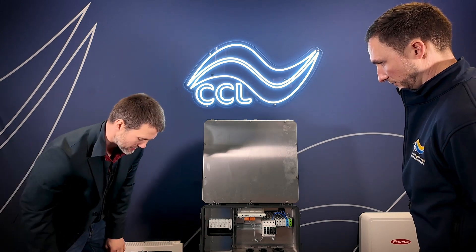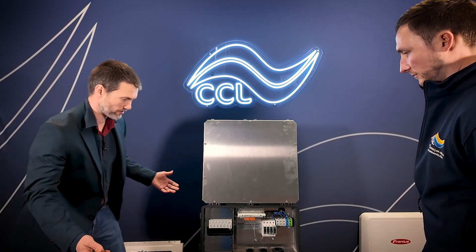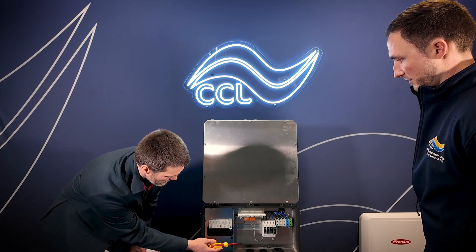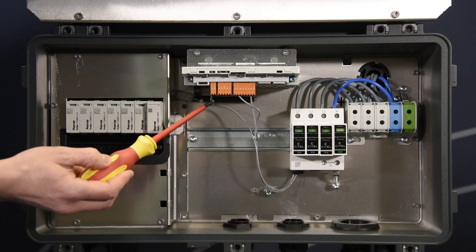Over on the left hand side, we've got the DC connection area. Underneath, you'll see we've got genuine Stäubli MC4s for a really secure, easy DC connection. We've got DC surge protection up here as well — again, replaceable in the field should you have a DC surge. In the middle, we've got a piece of DIN rail, so if you needed to connect any third-party components or monitoring systems, there's a space for them in here. And up in the top in the middle, we've got our pilot board, our communication card — the same communication card used in the Gen24 series of devices as well as the Tauro. So if you've commissioned either of those devices before, it should be a walk in the park.